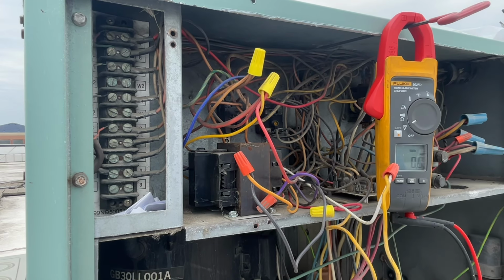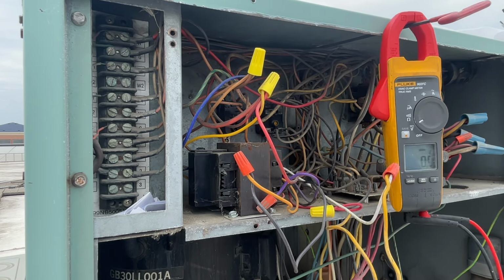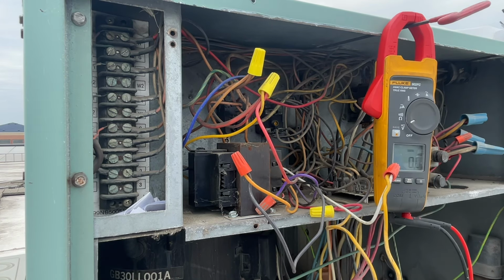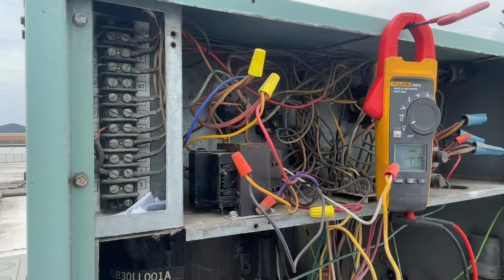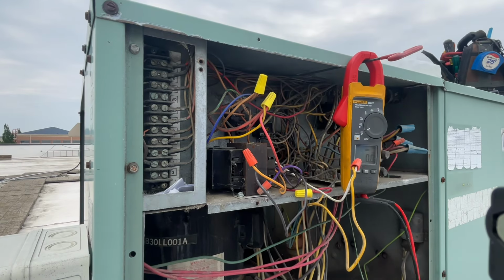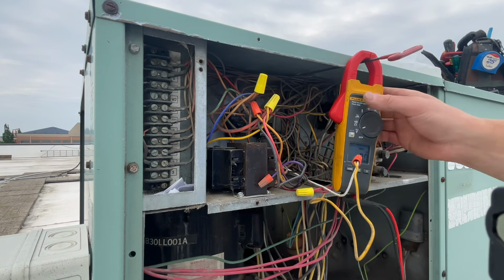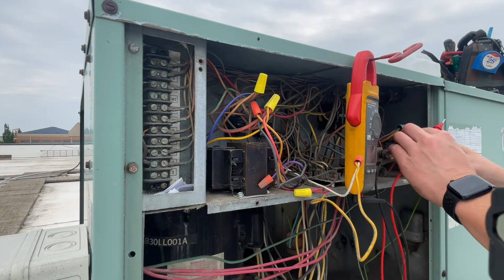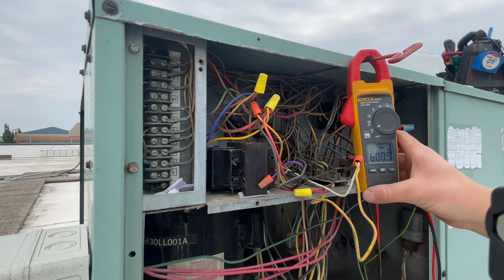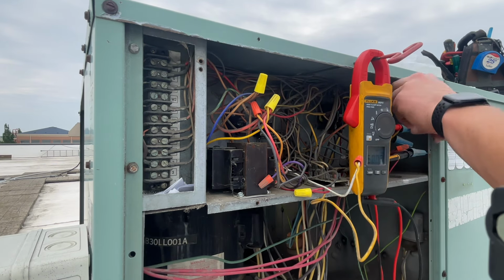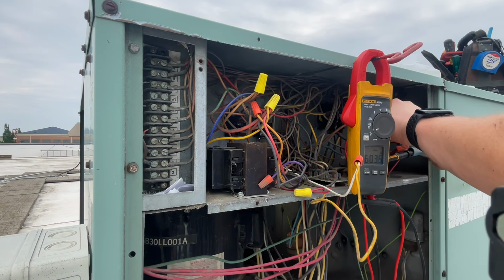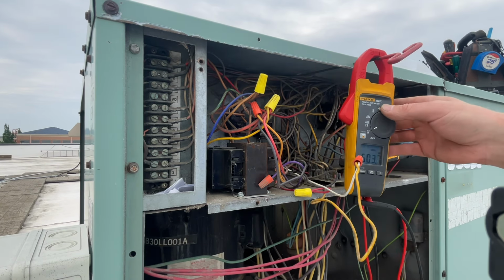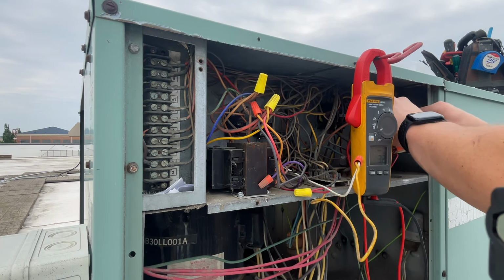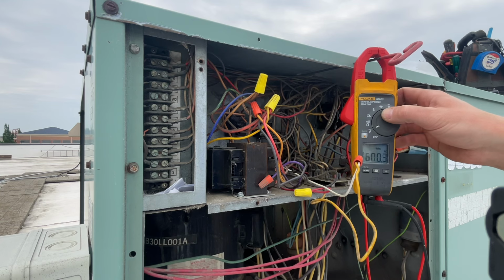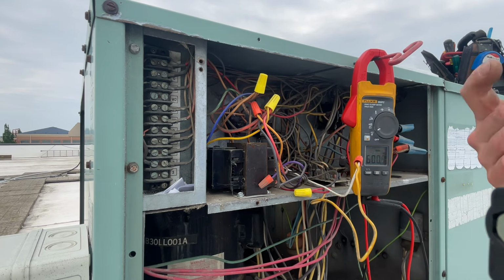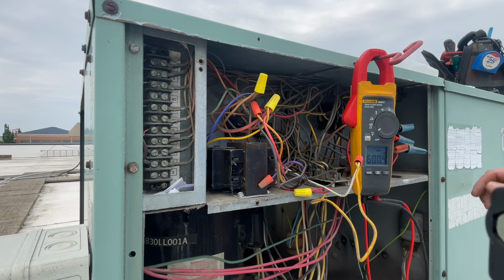They dehumidify. Anyways, I'm gonna show you how I came down to the conclusion that that big shoebox size transformer that weighs 40 pounds was defective. All right, so we'll turn our power on. And the first thing we'll do is we'll check our lines in from our disconnect. So if you watch my meter here, we're looking for 600 volts across all 3 phases. What do we got there? We got 600.9 from phase 1 to 3. Phase 1 to 2, 600.3. And then from phase 2 to 3, 600.6. So we know we got our inlet power. Our fuses are not blown, our breaker's not tripped. We're good on the inlet side.